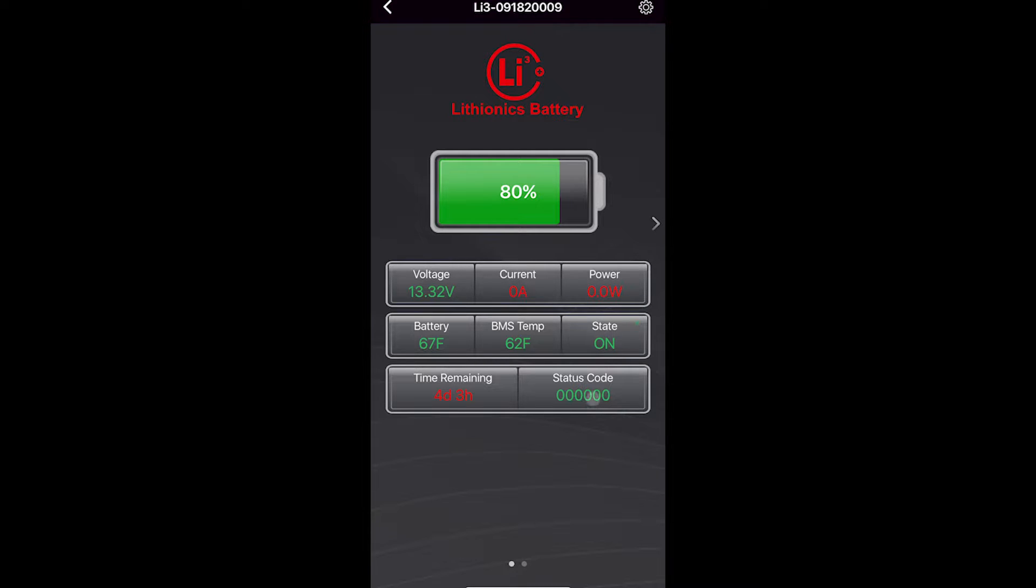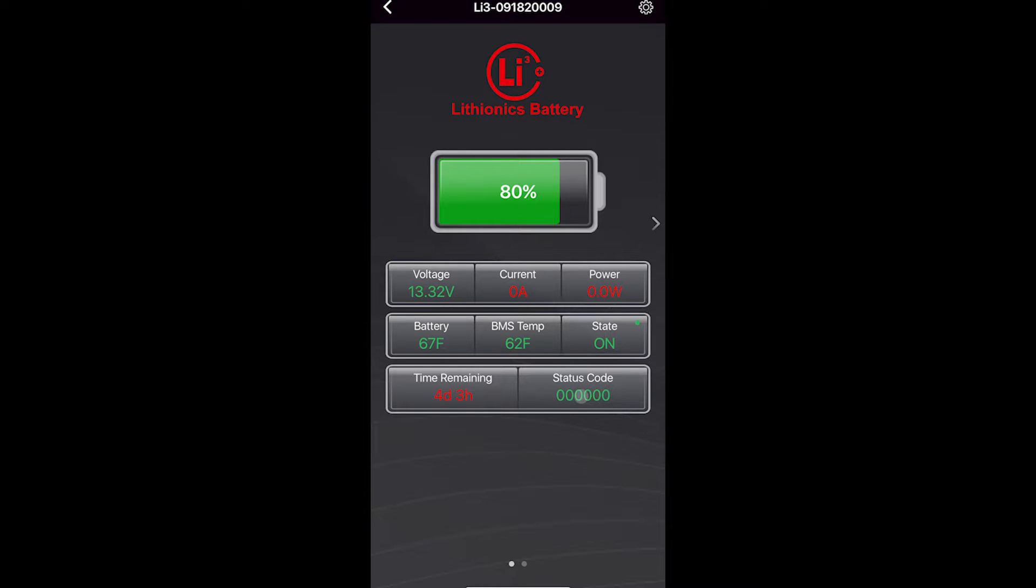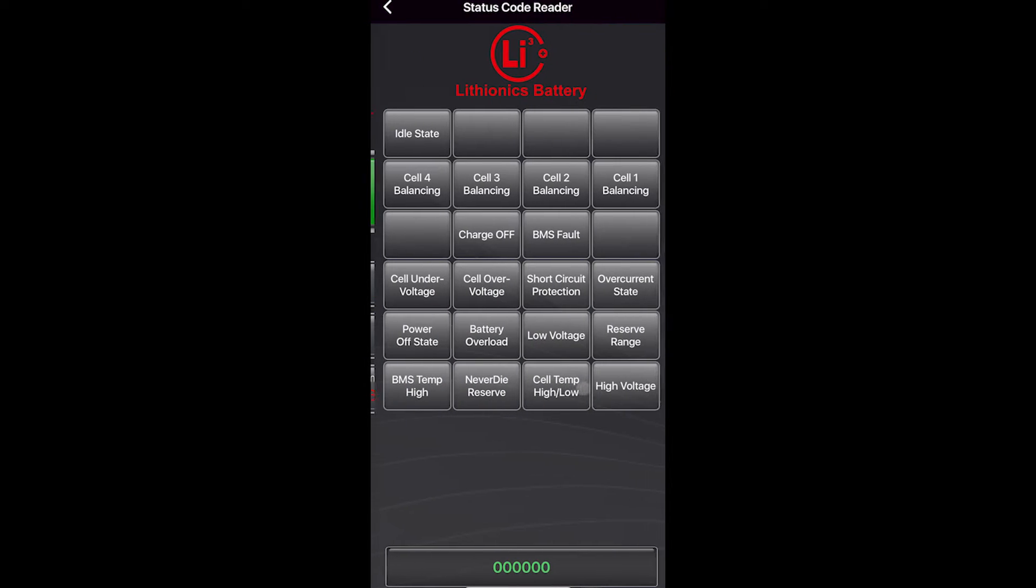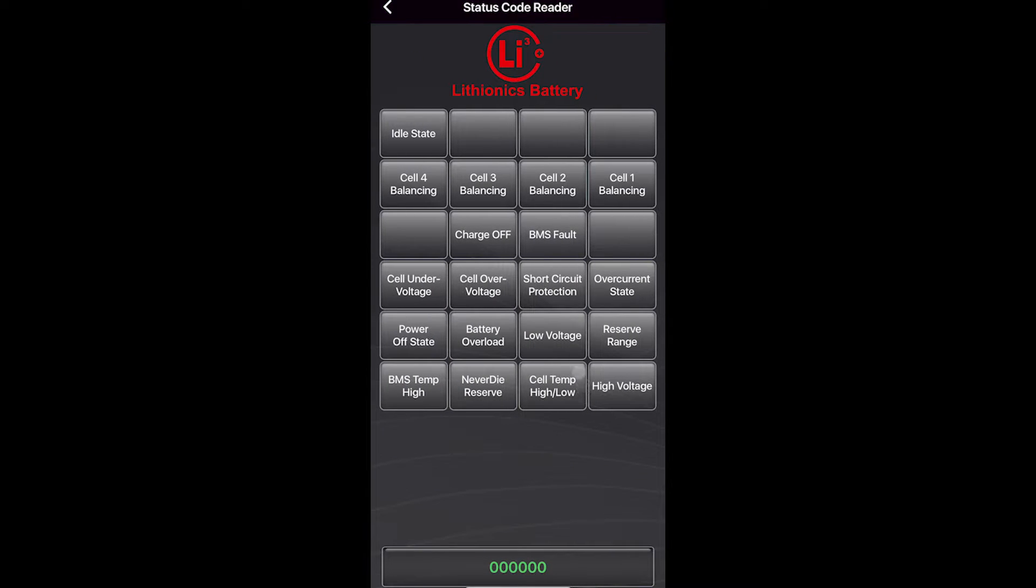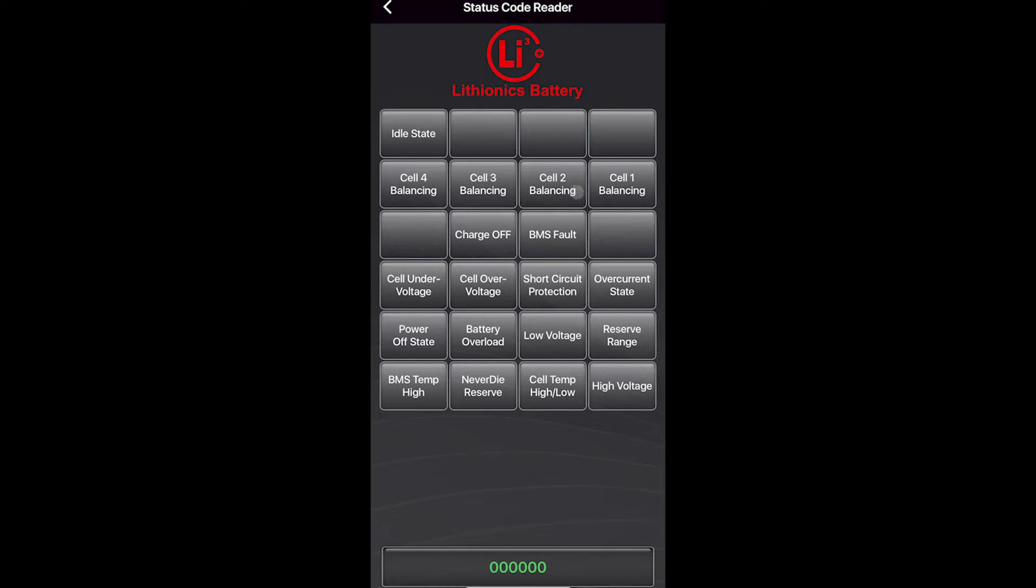The next thing that you see here is status code. When this is all zeros, there's no code. This is actually a hexadecimal number that has to get decoded to binary and looked up in a chart. If you don't know what that means, all you have to do is click the status code and it will go to this screen here, which if there's a code, any one of these cells will be highlighted to tell you what's going on.